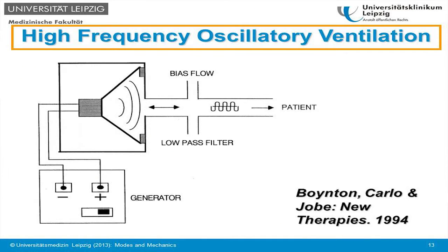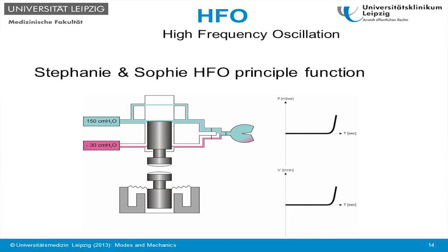These ventilators can also increase the frequency, and when we get high frequency oscillatory ventilation, this is accomplished by a membrane driven by a high frequency generator moving the air. Here's the bias flow going through, and the moving air is applied to the patient. There are also other principles generating high-frequency ventilation. The Stefan uses a valve alternating between a high and a low pressure source, which is alternately connected to the patient's lung, and thereby high-frequency ventilation is being generated, and there are other techniques on the market.